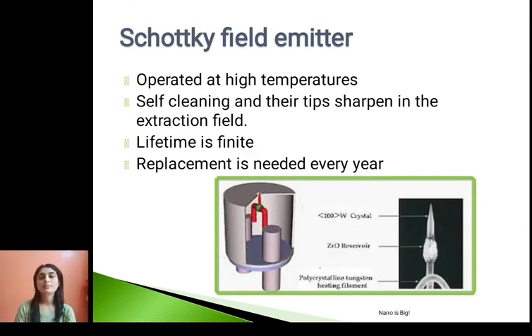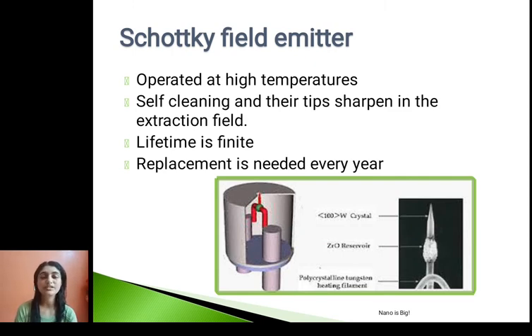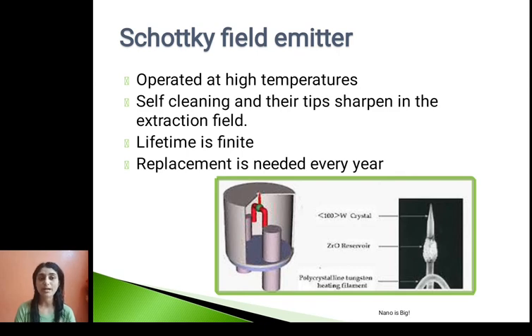The Schottky field emitter (SFE) is generally operated at very high temperatures. It has a self-cleaning property and the tips sharpen in the extraction field, so cleaning the tip is not a problem.